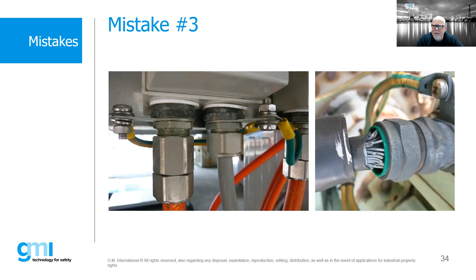Go to this slide. Again, you see a lot of issues with cable glands. On the left-hand side, what we've got, we have IP washers, and it looks like everything looks fine there. We have earth tags. Everything looks okay there. We obviously have a situation with our cable being pulled out of the back of the armor. We need to be aware of that. On the left-hand side, one of the requirements is that generally speaking, with certain glands, we have to remove the plastic tape around the internal bedding. On the left-hand side, it shows that that tape around the bedding hasn't been removed, so that's an issue.